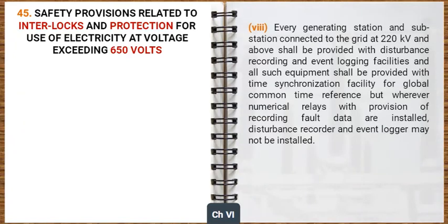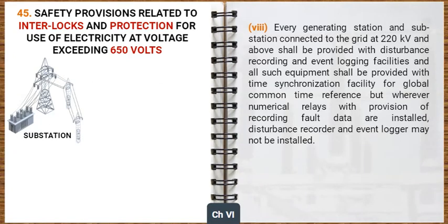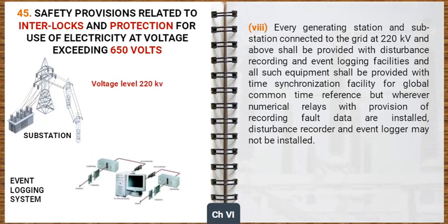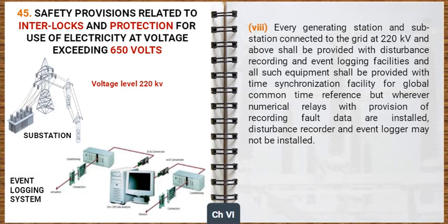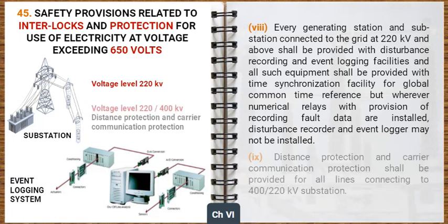Every generating station and substation connected to the grid at 220 kilovolt and above shall be provided with disturbance recording and event logging facilities, and all such equipment shall be provided with time synchronization facility for global common time reference, but wherever numerical relays with provision of recording fault data are installed, disturbance recorder and event logger may not be installed. Distance protection and carrier communication protection shall be provided for all lines connecting to 400 or 220 kilovolt substation.